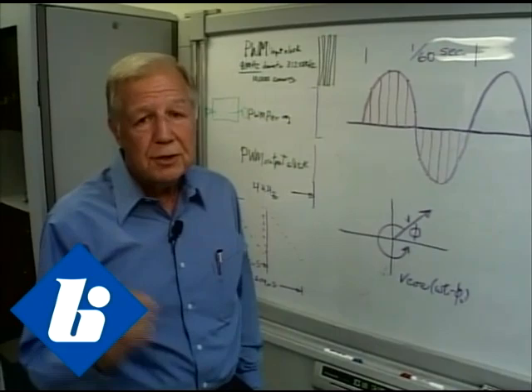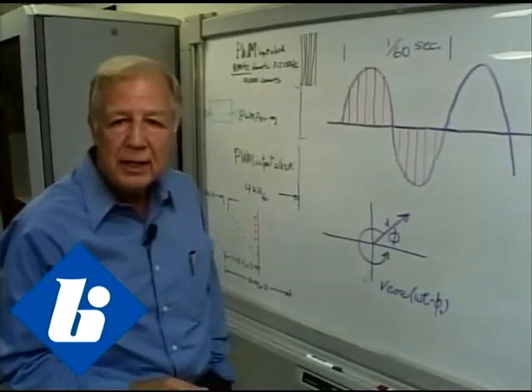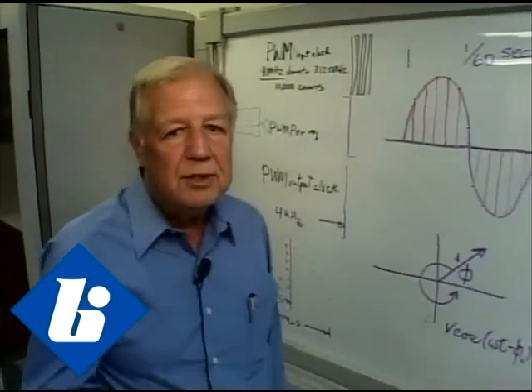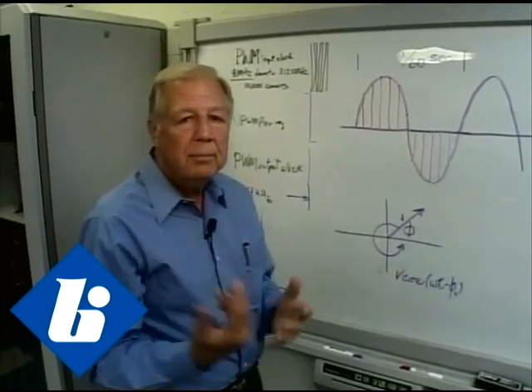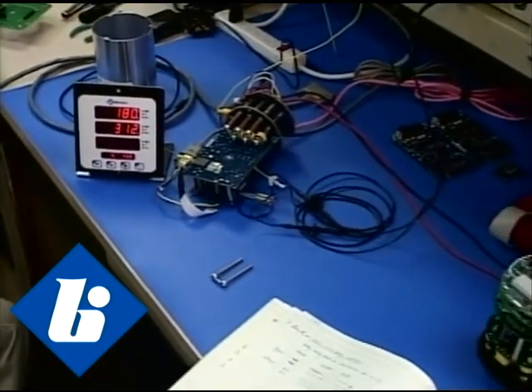We have to withstand wide temperature variations, mechanical shock, as well as electrical surges. What we do with Bitronics and other digital instruments is we take thousands of samples per second of the values. The trick is to take those samples, put them through mathematical algorithms, and turn them back into not just volts but amps, watts, vars, and also look at any small variations — picking up the quality of that power — which is important for some industrial customers as well.